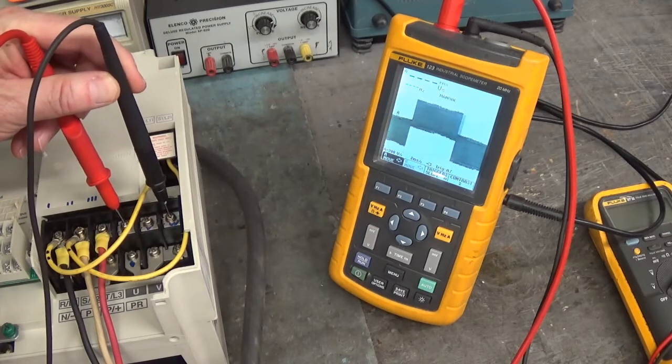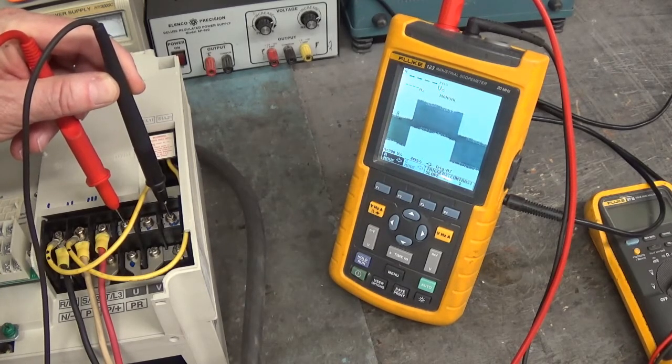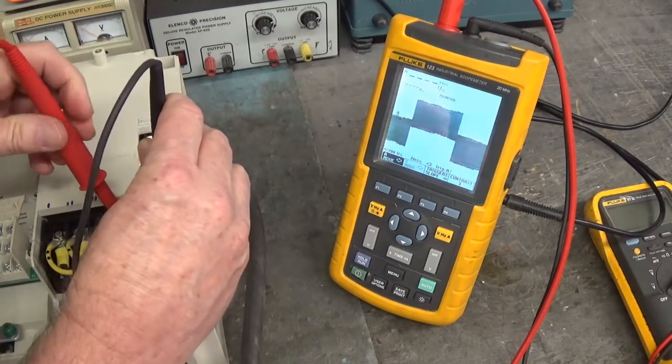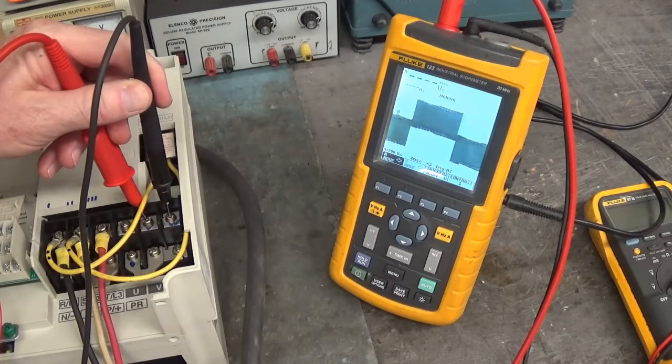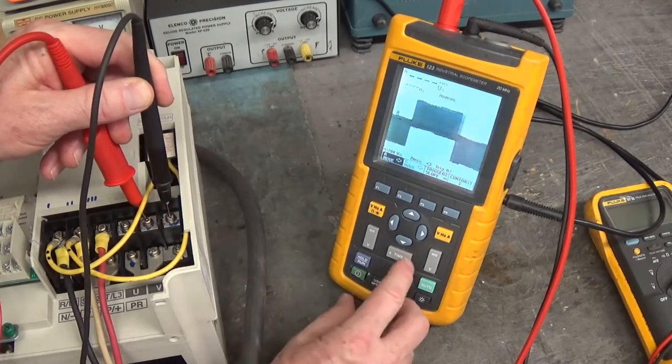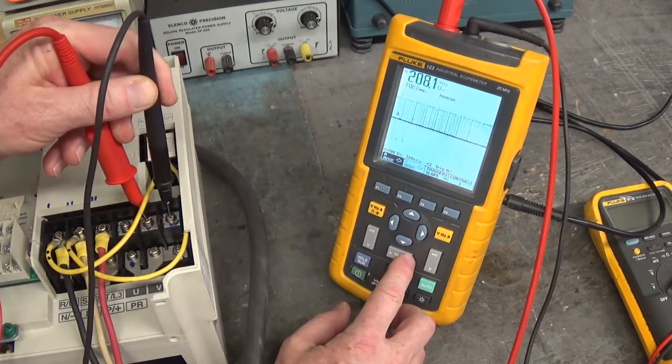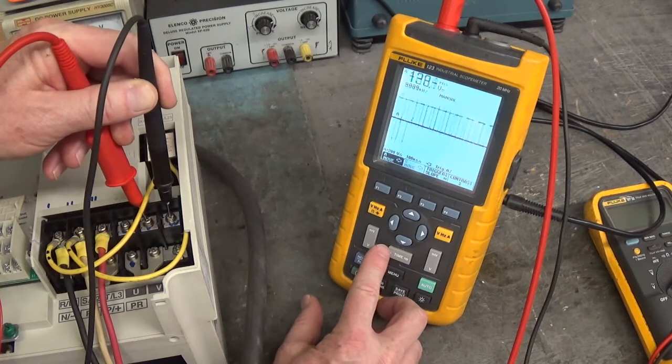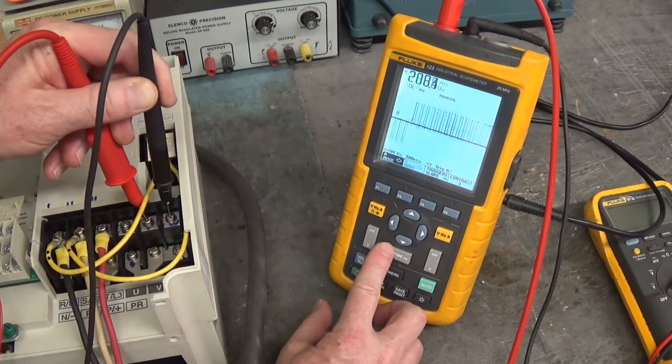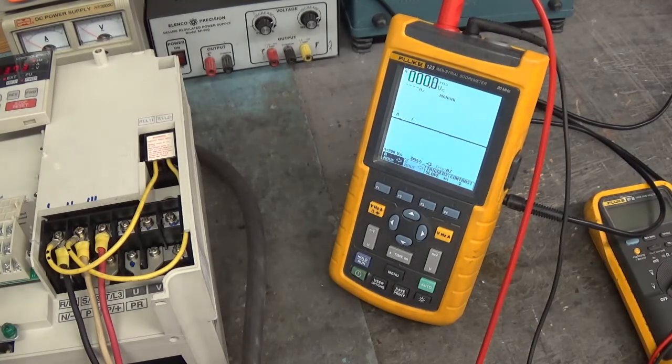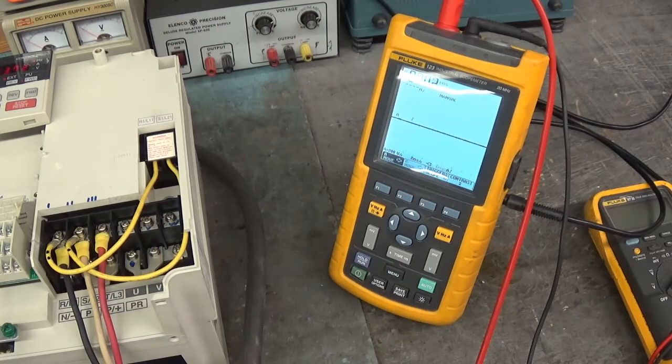Let's go look at U to W. Okay, it looks the same. That's good. Now let's look at V to W. There we go. That looks good. Let's spread it out so you can see the PWM. There's the pulse width modulation.